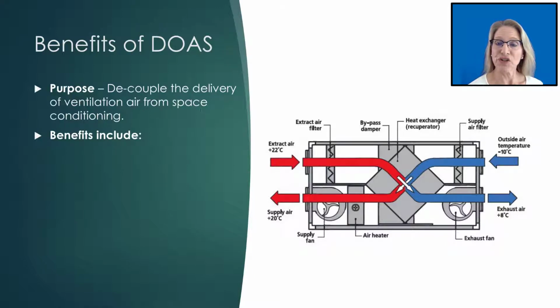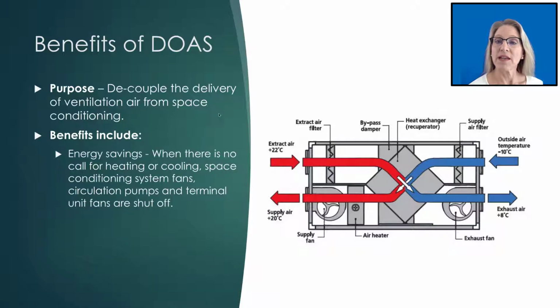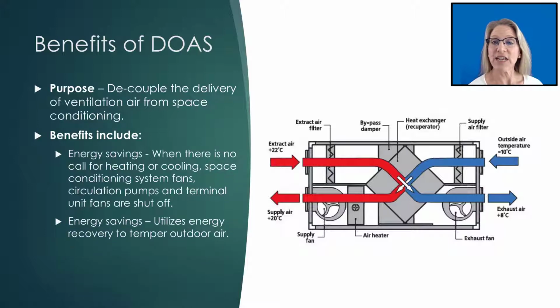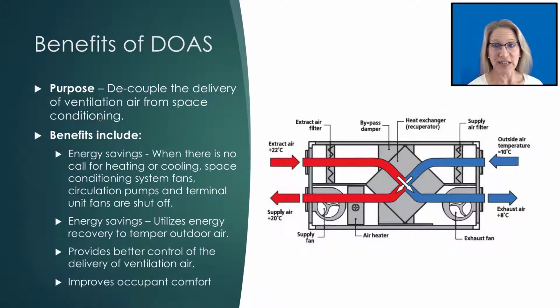This system approach provides energy savings in two ways. Decoupling ventilation from heating and cooling enables the space conditioning system fans, circulation pumps, and terminal unit fans to shut off when there's no call for heating or cooling. This provision also requires energy recovery, which reduces the amount of heating energy required to temper the outside air. This approach provides better control of the delivery of ventilation air to the space, which in turn can improve occupant comfort.